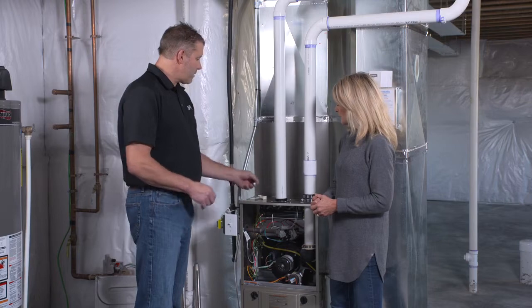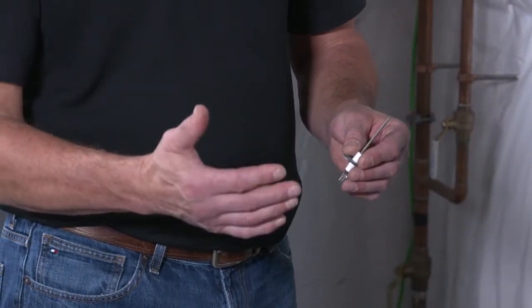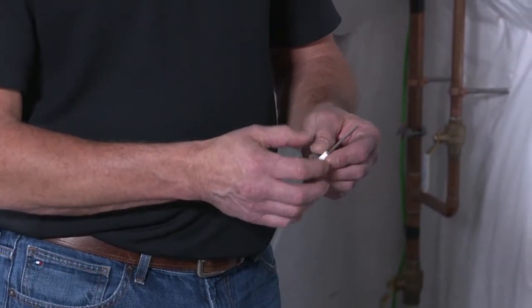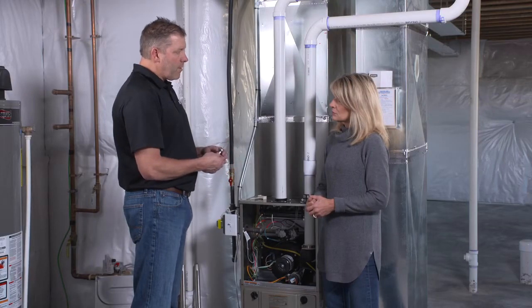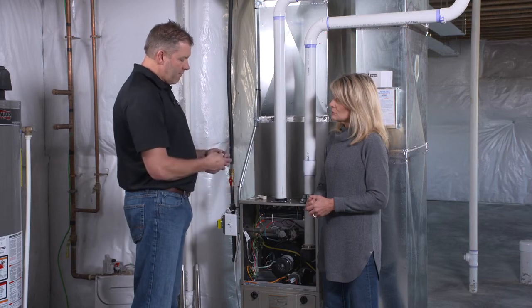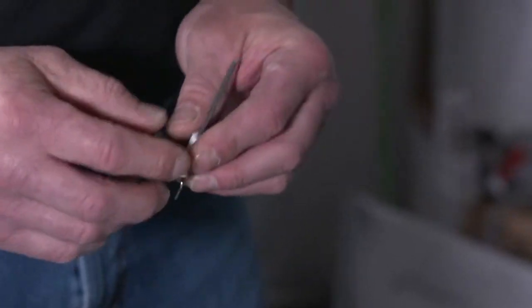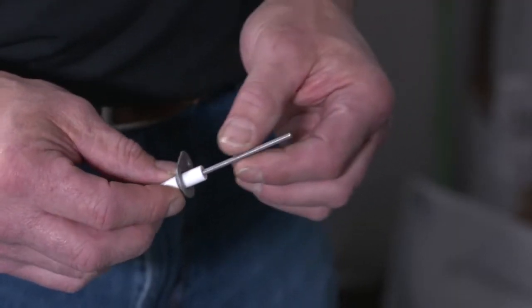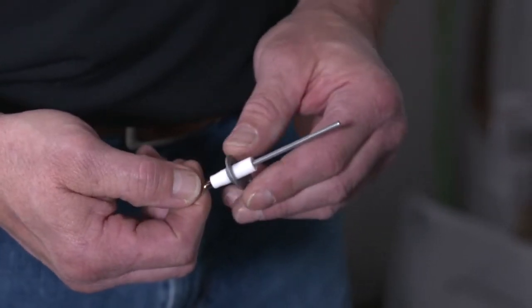There are also flame sensors in your furnace. This steel rod heats up, and when that furnace lights, it has to get this rod so hot within less than two seconds. In furnaces located in a laundry room, basement, or utility room, contaminants collect on this rod, coating and insulating it, causing nuisance failures — it'll be on and off. So we can inspect it, clean it, and test it. It's porcelain, so if it's cracked, we can visually identify that and know whether we need to replace it.